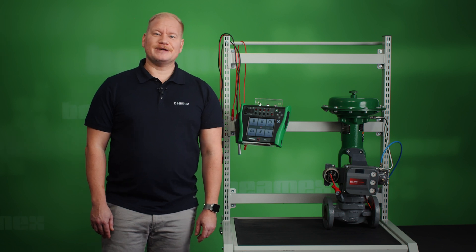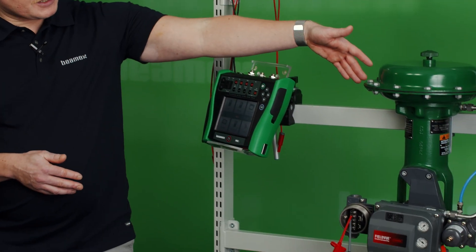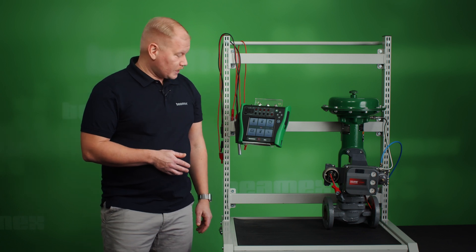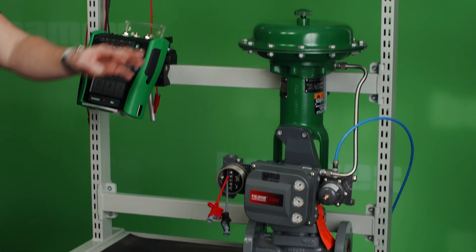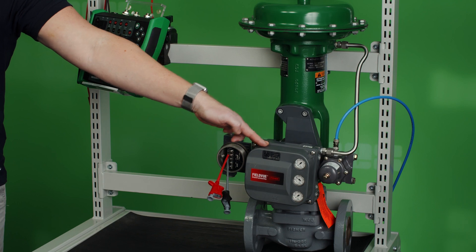Hi, I'm Sebastian from Beamex. In this video you will learn how to connect the MC6 to a HART-operated control valve and to perform a linearity test for the same valve. What you see here at the bottom is the valve itself. On top we have an actuator and in front we have the digital valve controller.